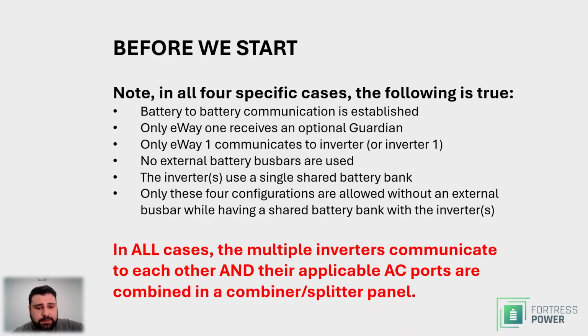Splitter panels come into play when you have external AC source. Let's say you have grid and you have 2 inverters. That grid connection should be established between the grid and inverter 1 and grid and inverter 2. So that's why you need a splitter panel, so you can essentially, quote unquote, split the grid signal to two inverters. And same applies to the generator port if you're using AC coupled PV or you're using a generator. This is just a side note, just for clarity.